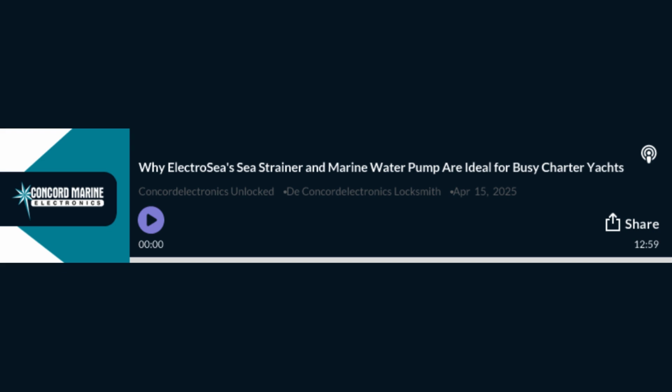They're a really common failure point. They wear out, they crack, salt water gets in. It causes all sorts of problems. Yep, seen that plenty of times. So the magnetic drive in the Silver Bullet gets rid of that seal completely. It uses magnets to spin the impeller. No physical connection, no seal needed. Ah, clever. So no seal leak. Exactly. Eliminates a major source of leaks and potential mechanical failures right there.